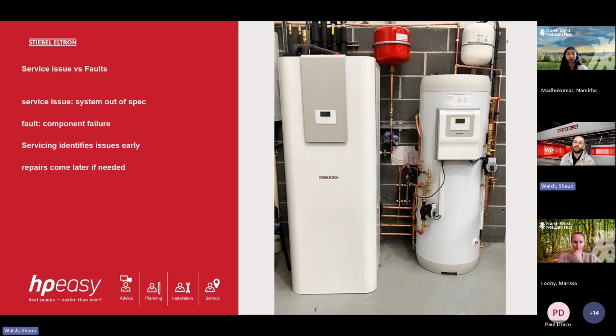So the next thing we look at is service issues versus faults. Faults and servicing are two separate issues, really. Not every fault that the machine has necessarily needs a repair or a replacement component. They just need attention, for example. If we were looking at the expansion vessel and the system pressure drops to 0.5 bar, we don't need to replace any components. We just need to top it up with some water and some inhibitor, and that takes us back to normal system pressure. That problem has been resolved then.